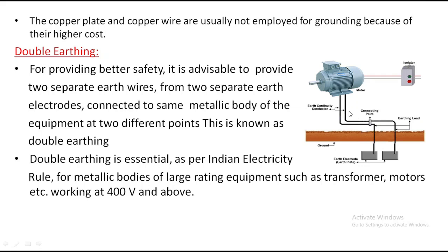And what is the use? If one fails, the other is applicable. That is the main reason. Whenever we use these parallel conductors, the resistance automatically decreases greatly, and as the resistance decreases, the leakage current capability increases. Look at double earthing: for providing better safety, it is advisable to provide two separate earth wires, from two separate earth electrodes connected to the same metallic body. Look here, for the same metallic body, two separate earth electrodes.